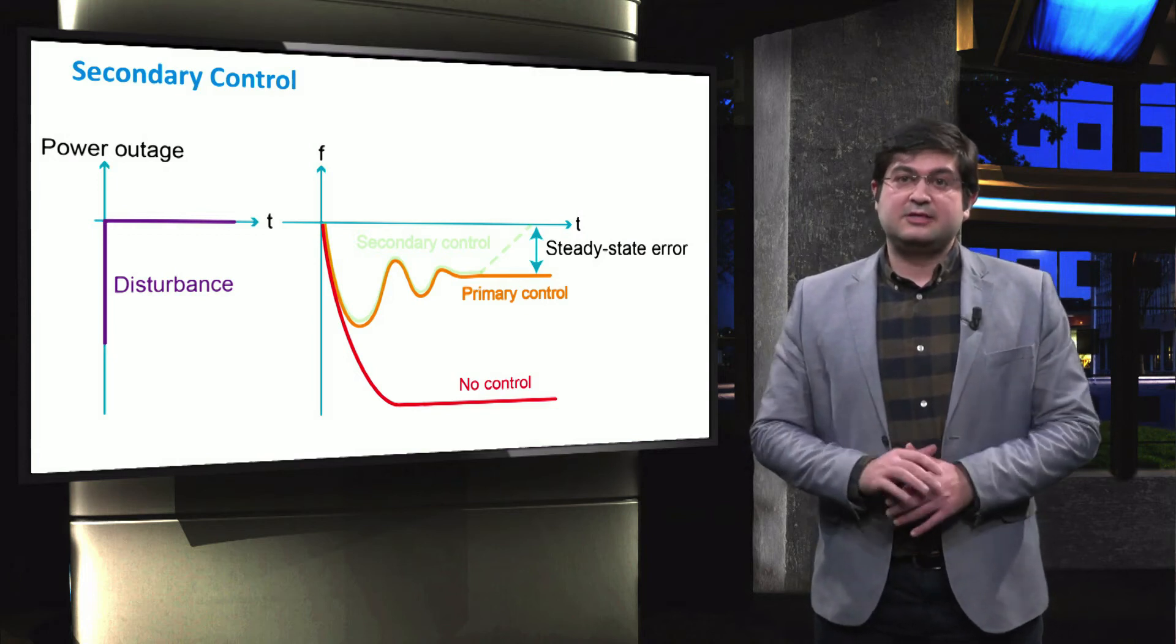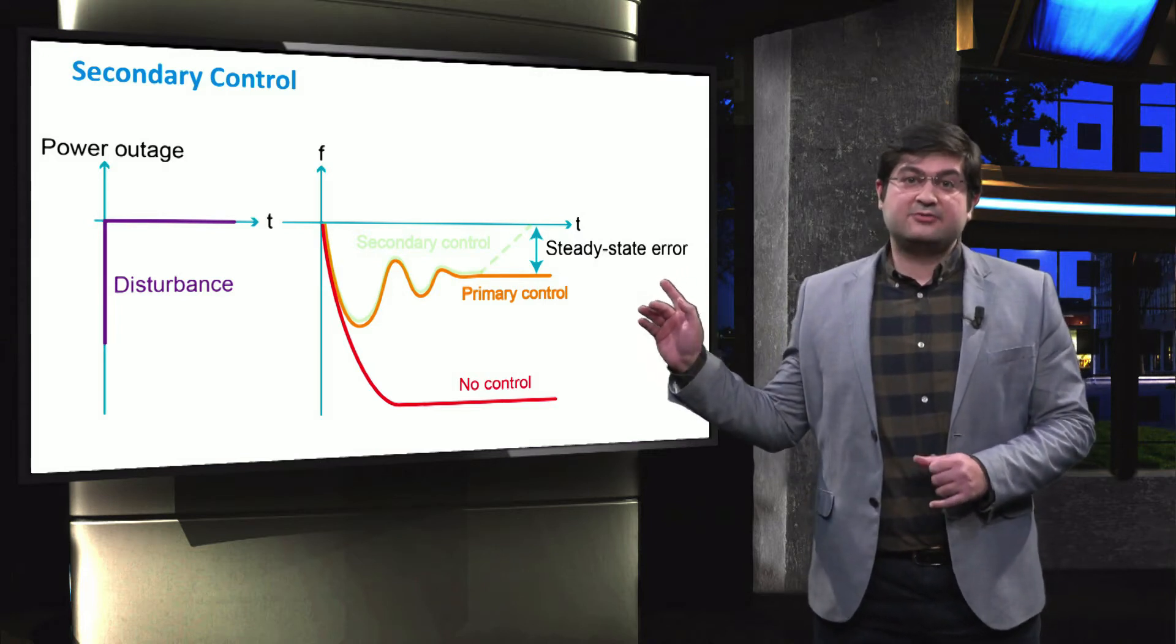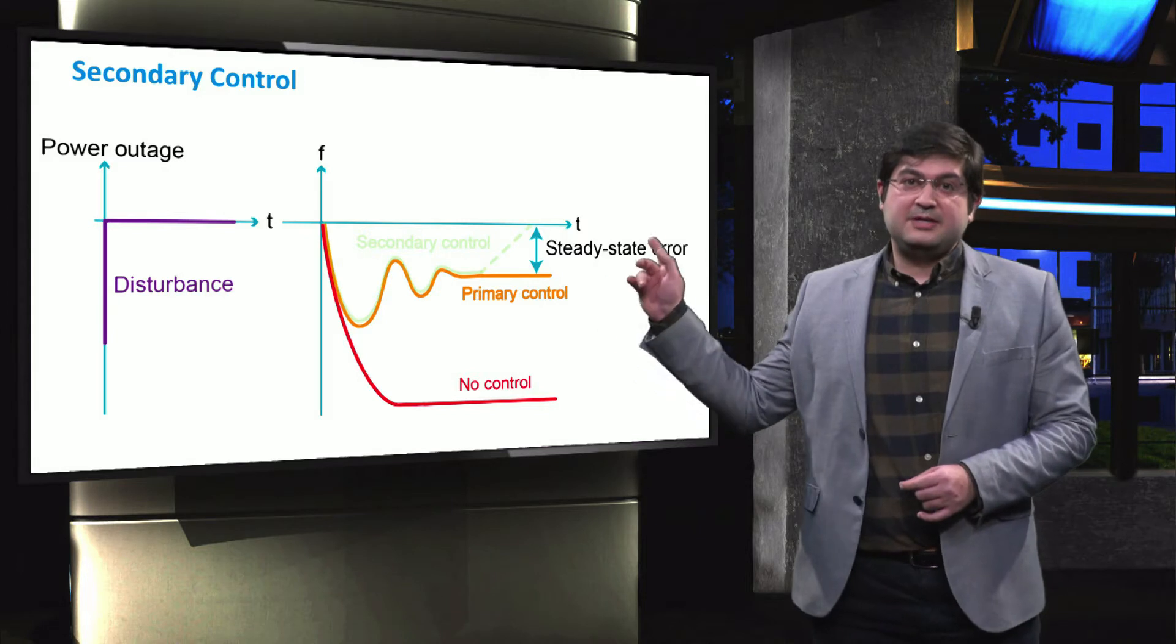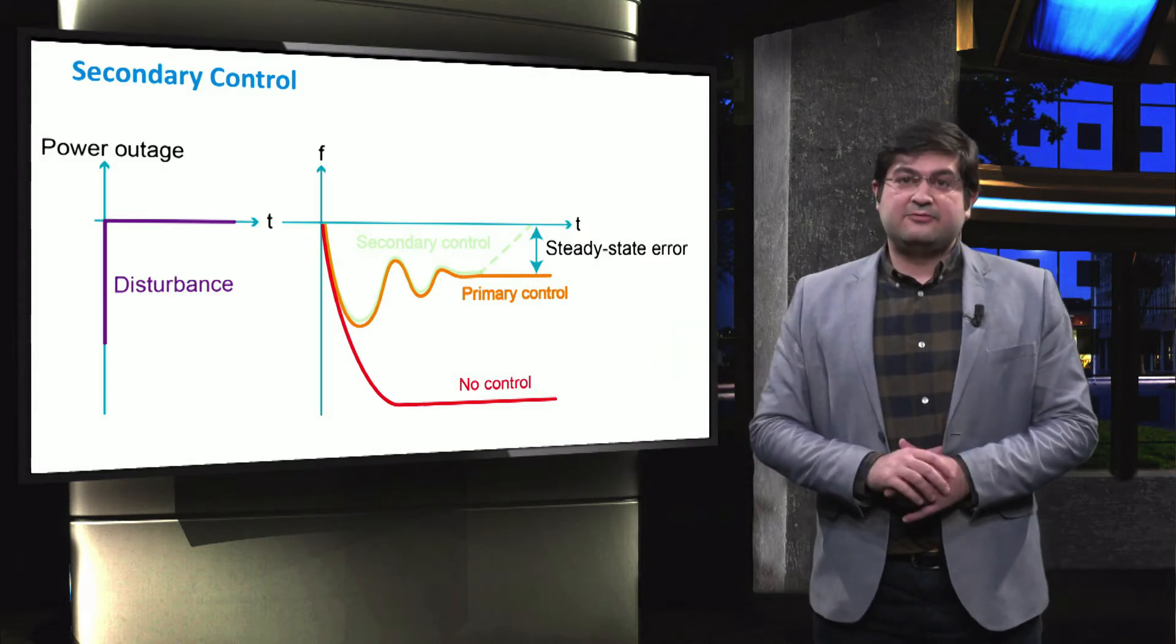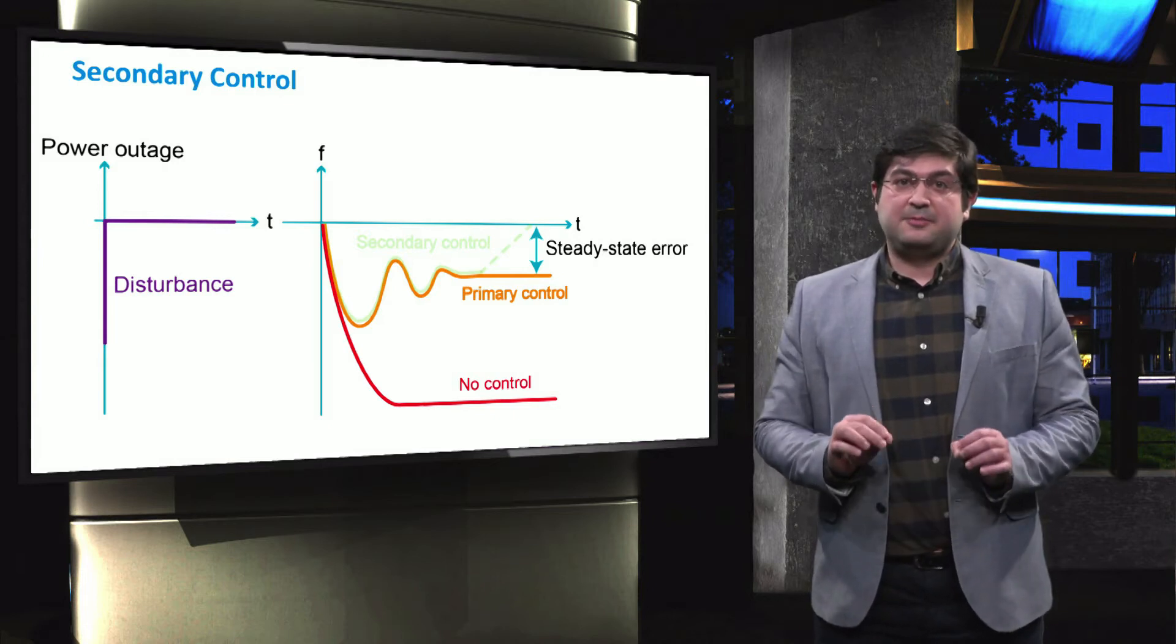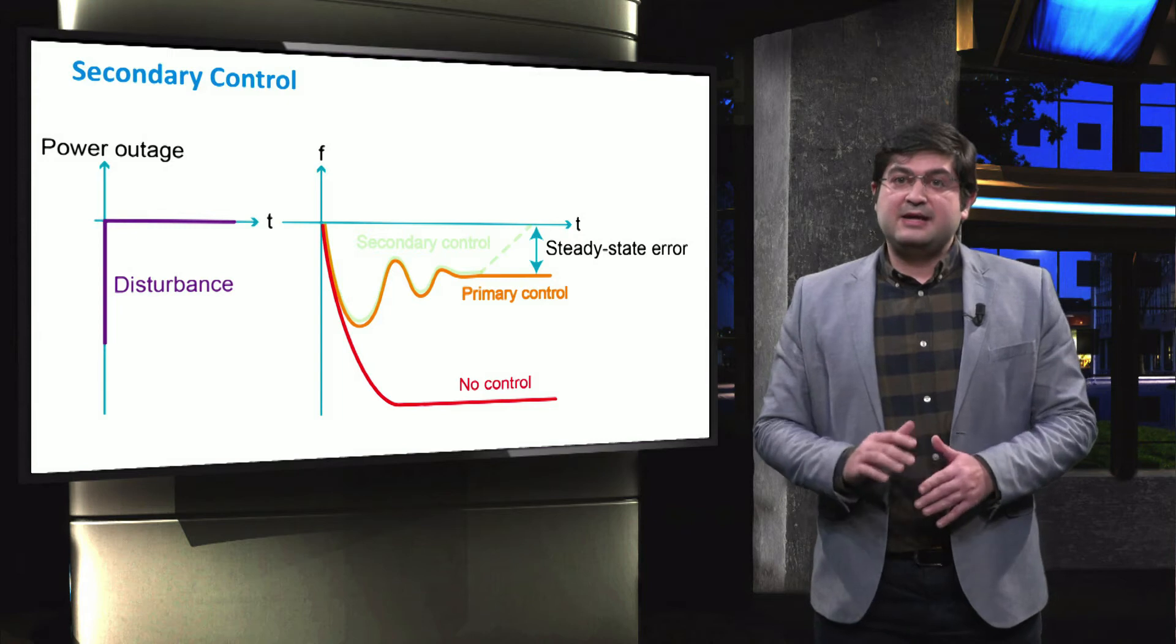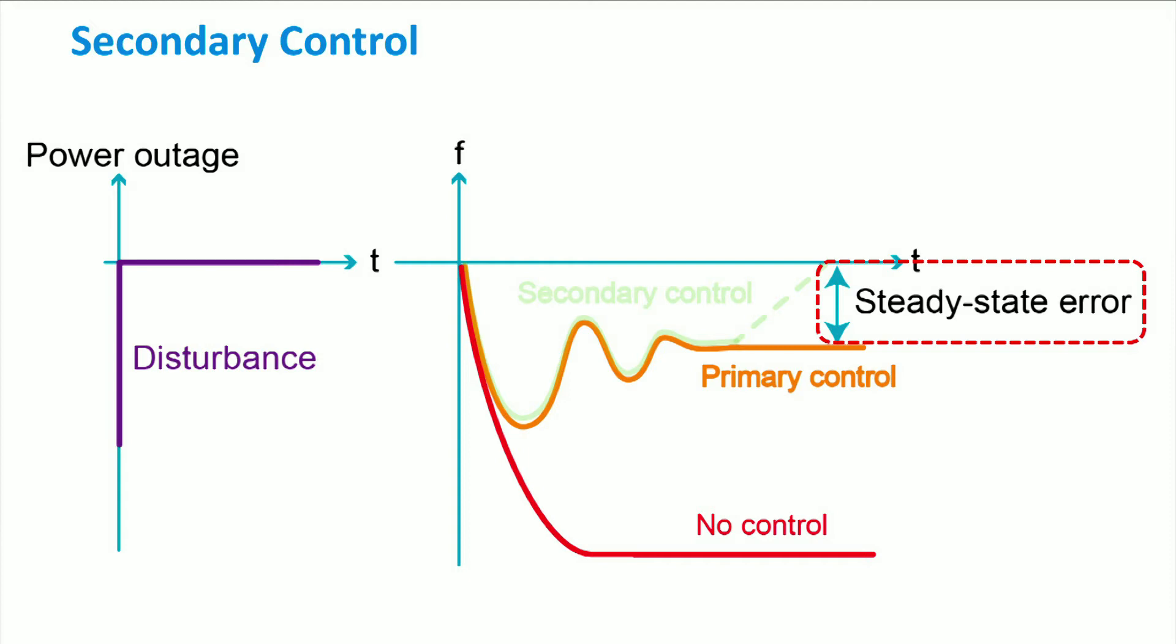If the primary frequency control is implemented, then the large frequency deviations right after the disturbance can be effectively suppressed. However, as it can be seen, the frequency does not go back to the rated value using the primary frequency control, and remains at a steady state value below the nominal one. As the system shall operate always at the nominal frequency, this steady state error shall be eliminated.